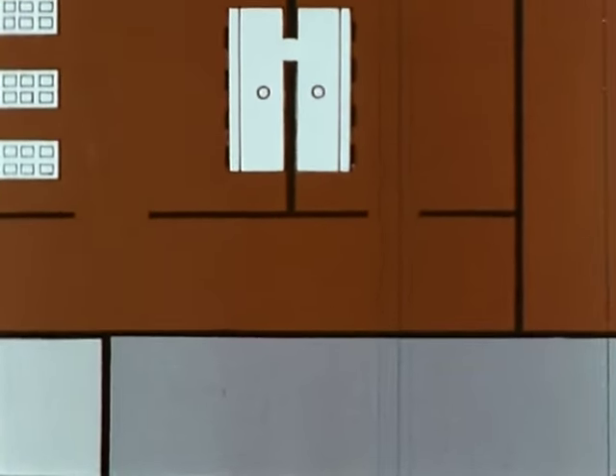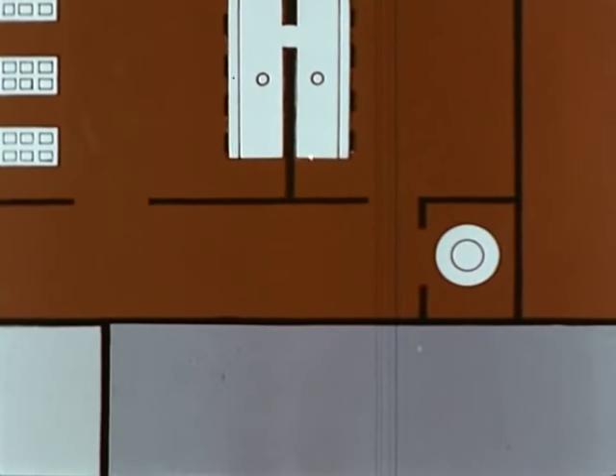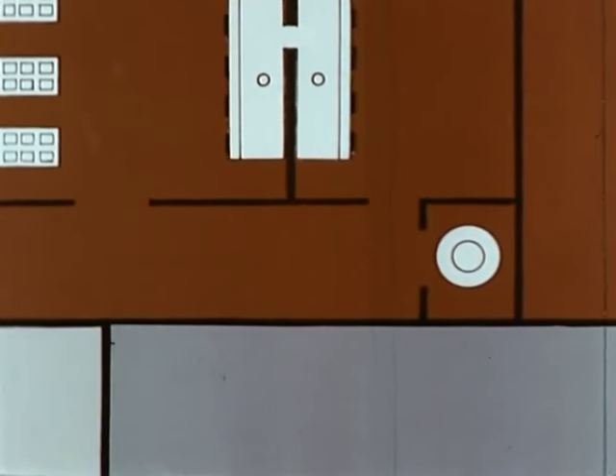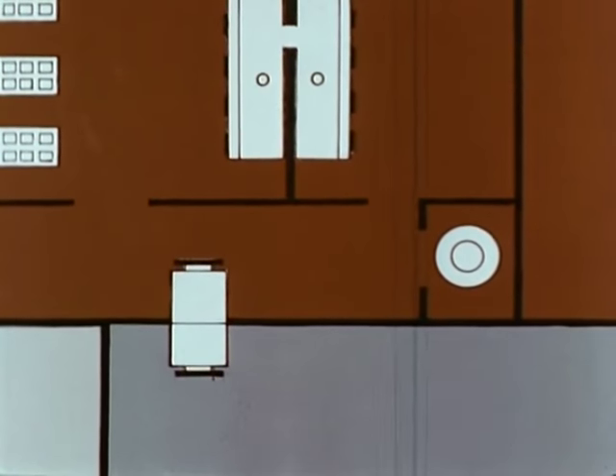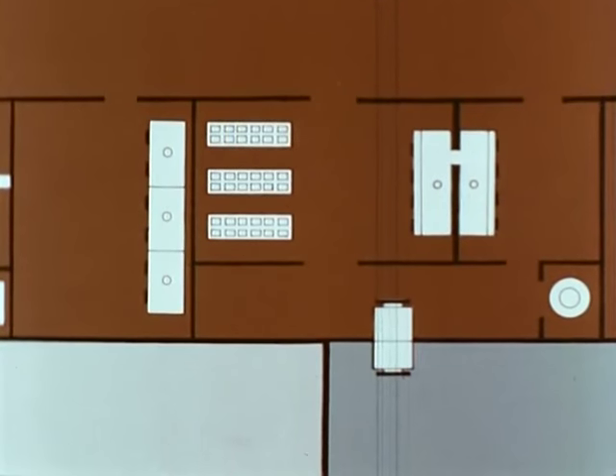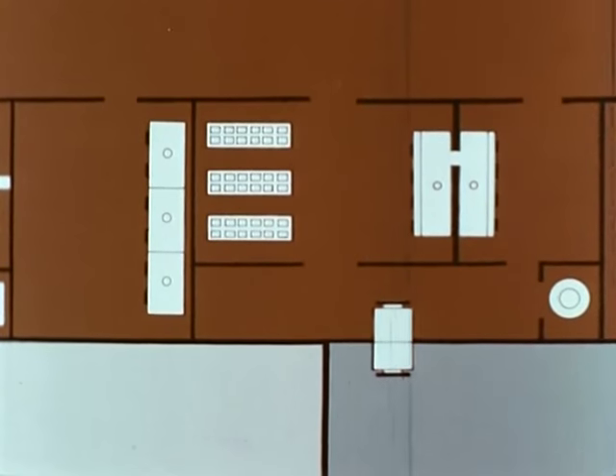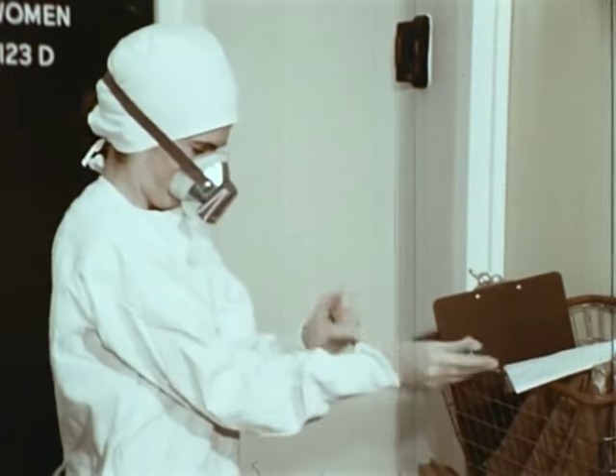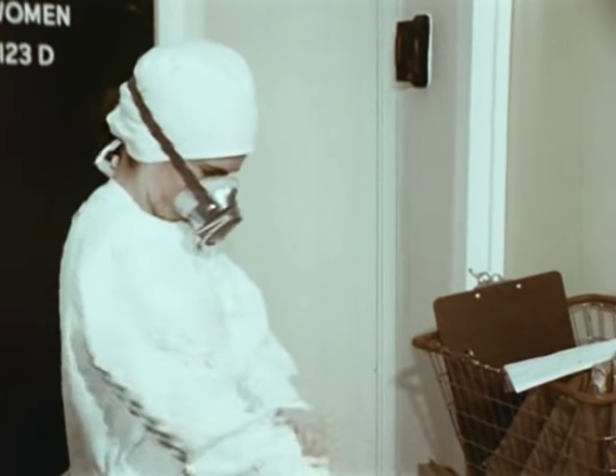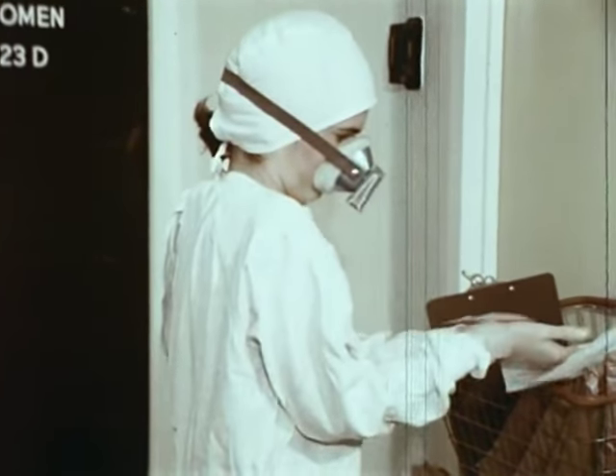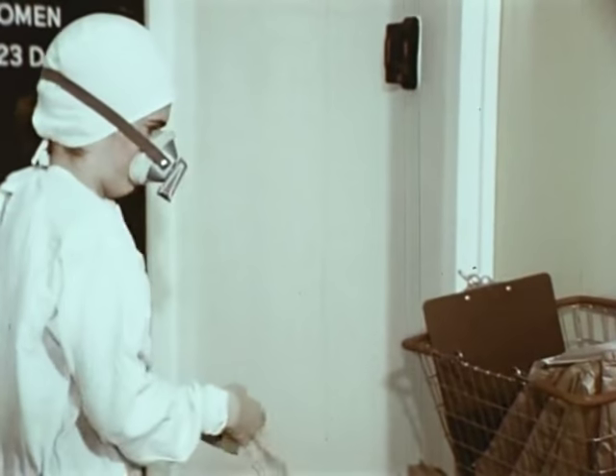Also, if not available elsewhere, the animal area should have an incinerator for disposing of animal carcasses and a large autoclave for sterilizing cages and passing them into a cage washing room. In designing this research area, the type and degree of animal isolation should be considered early. It should always provide for safe working conditions for lab personnel and prevent undesired animal cross-infection. In rooms housing small infected animals, the hazard level is sometimes high enough to require that protective clothing and respirators be worn by laboratory personnel.